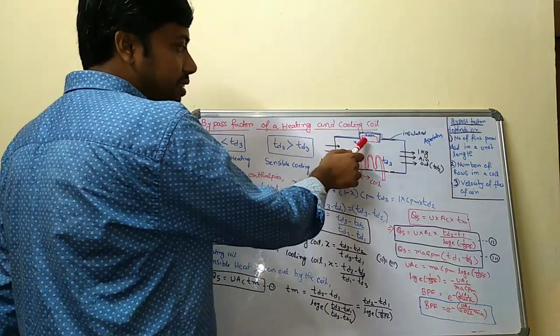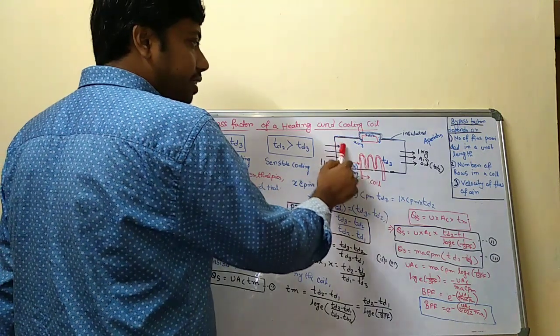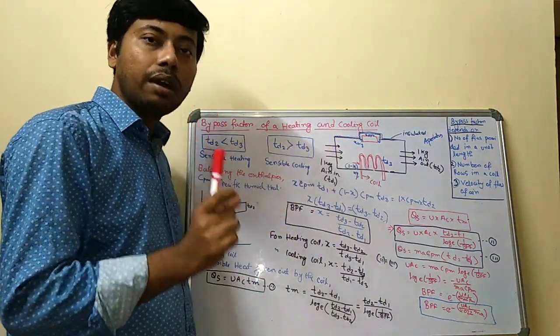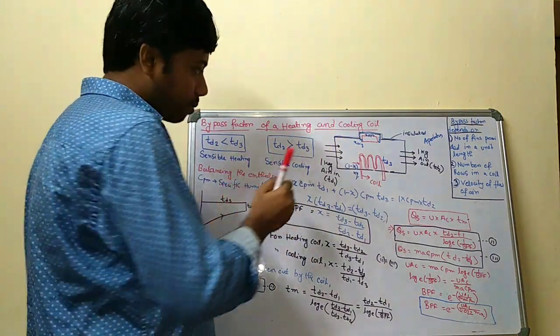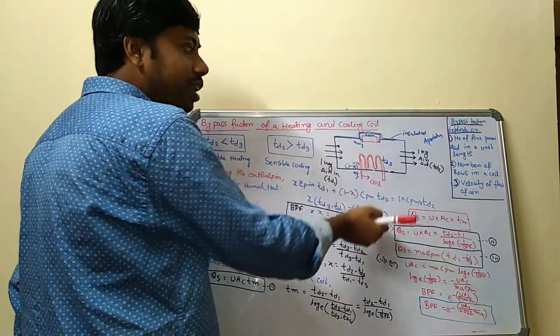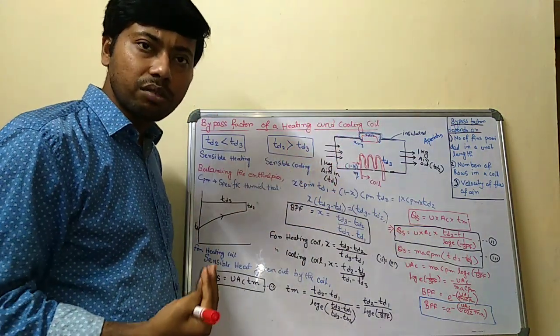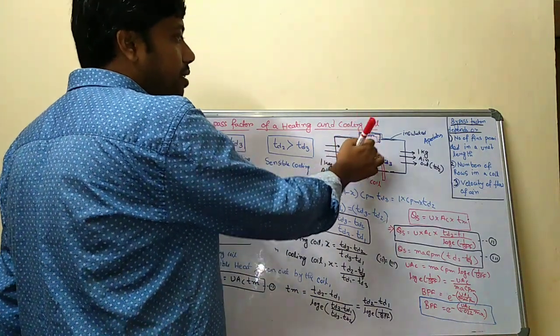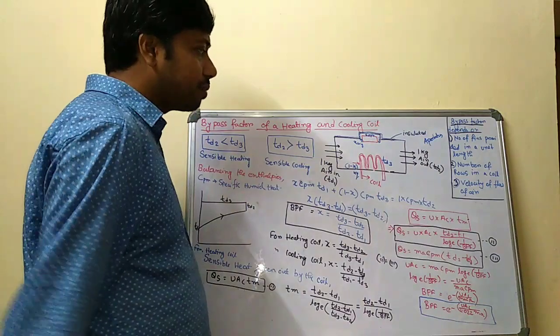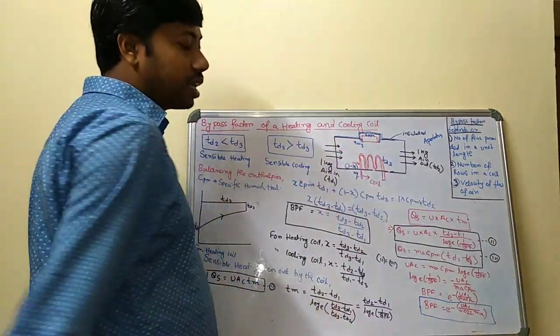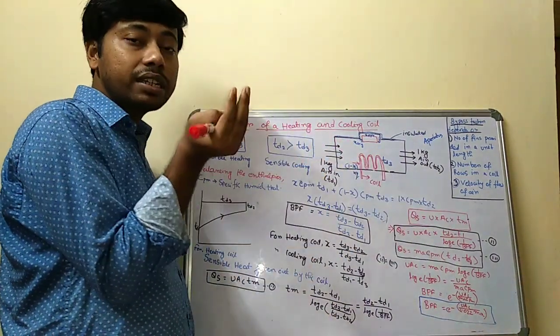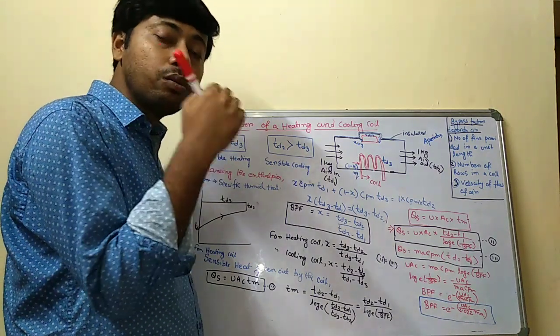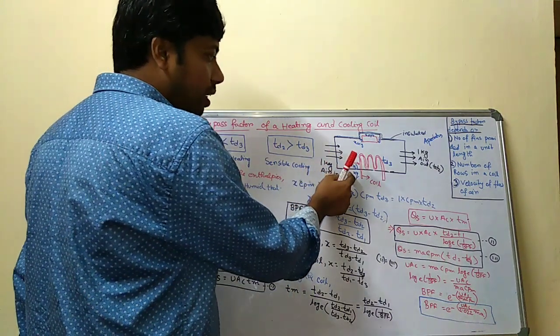Because the x kg is not directly contacted with the coil, the efficiency of the coil is not 100%. So this x kg bypasses through the chamber but doesn't contact the coil directly, and the amount of directly contacted air is 1 minus x kg.